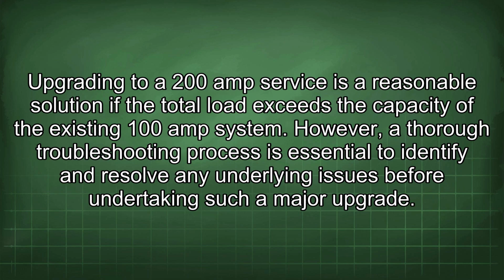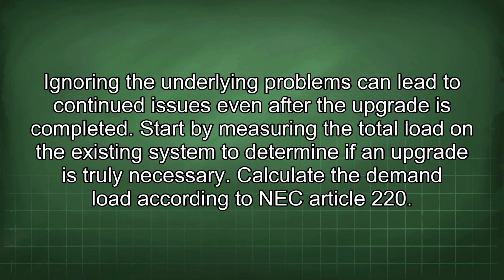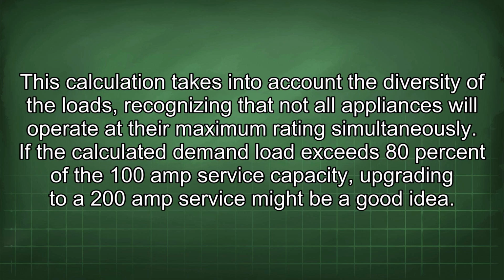Upgrading to a 200 amp service is a reasonable solution if the total load exceeds the capacity of the existing 100 amp system. However, a thorough troubleshooting process is essential to identify and resolve any underlying issues before undertaking such a major upgrade. Ignoring the underlying problems can lead to continued issues even after the upgrade is completed. Start by measuring the total load on the existing system to determine if an upgrade is truly necessary. Calculate the demand load according to NEC Article 220. This calculation takes into account the diversity of the loads, recognizing that not all appliances will operate at their maximum rating simultaneously. If the calculated demand load exceeds 80% of the 100 amp service capacity, upgrading to a 200 amp service might be a good idea.